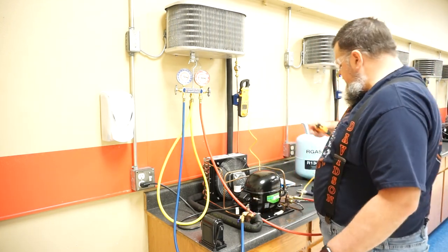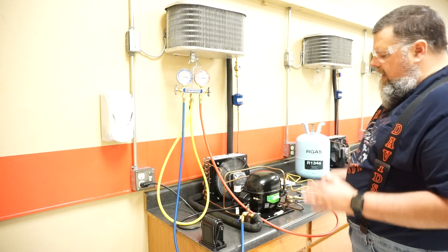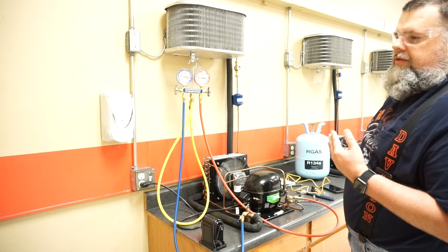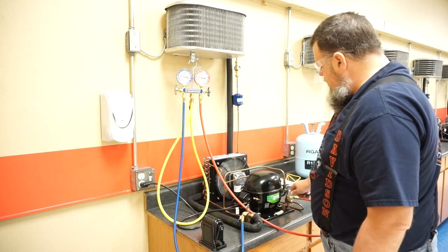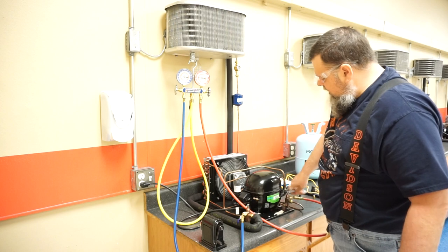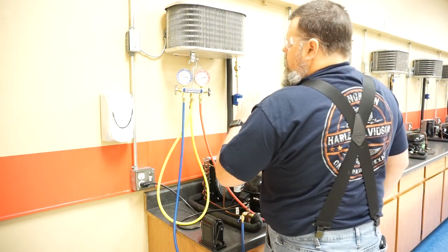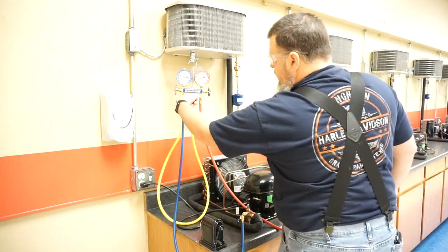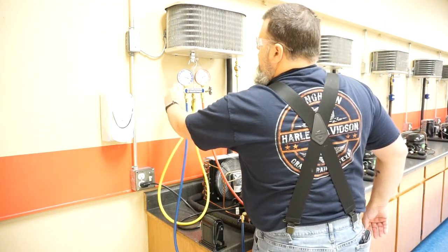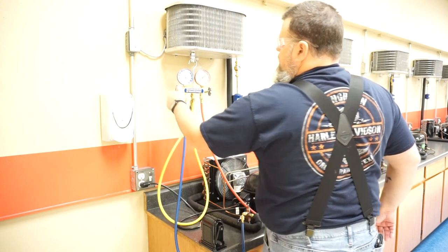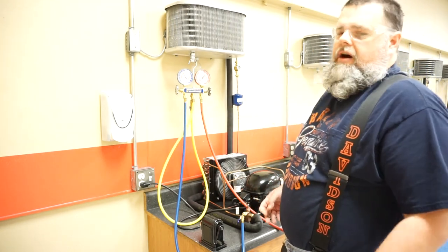Go ahead and get ready to dismount this system. This is how we get the liquid out of our gauges. Now you can use your low loss fittings on this, but low loss is mainly for Schrader valves. Schrader valves are something we'll deal with in a later video. What I want to do first, I want to backseat this valve. The stem's going to be all the way up. I'm going to open my high side gauge. Now what I want to do is I want to flash the liquid because I've got liquid all the way up to here. I don't want any liquid in my gauges, I want it just to be vapor. So I'm going to flash it out. Once, twice, three times, and I'm just going to leave it open. Now these pressures are going to equalize with each other. So I'm actually putting the refrigerant back in the system instead of taking it off on my hose and just wasting it.